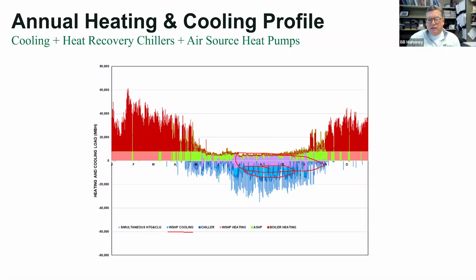That's this light blue area here, and that's cooling from the ground. So you're basically storing the heat in the ground, and then in the wintertime, we're going to pull that out. That's this salmon colored. So this cooling that we stored becomes this heating that we pull out of the ground in the fall, and we ran it all the way through the winter almost. So that's the use of the water source, ground source, geo-exchange heating system. And then we filled in some blanks here since, like we said, we've got a given amount of cooling that we were able to store. We only get that much heating back out.